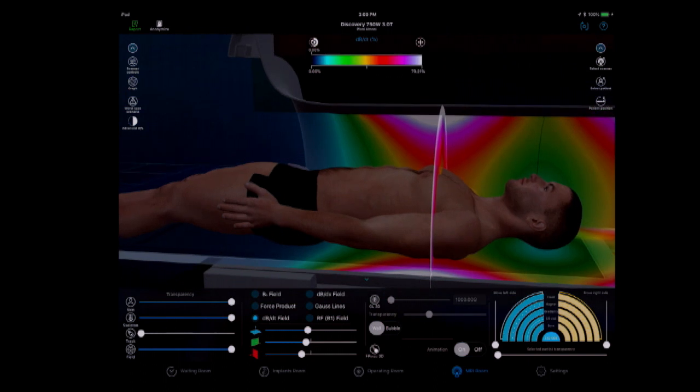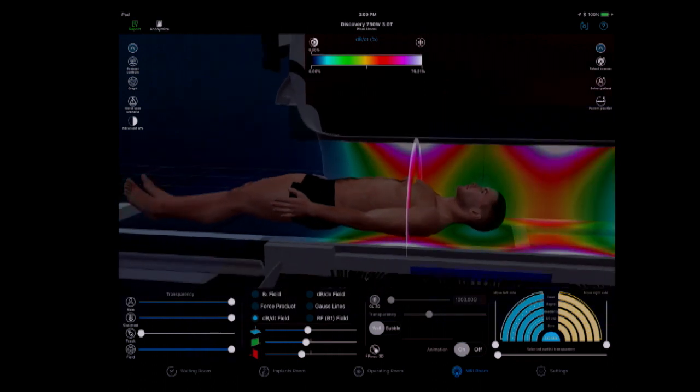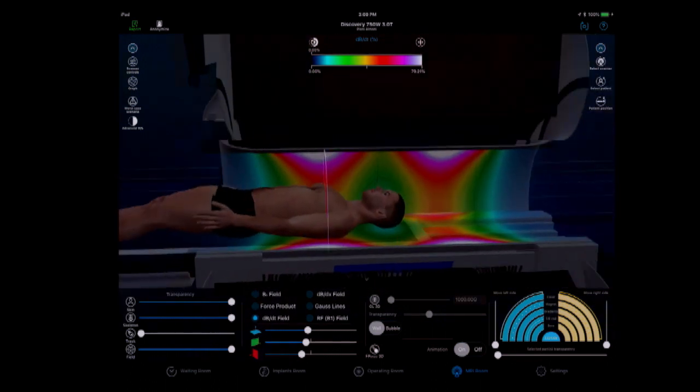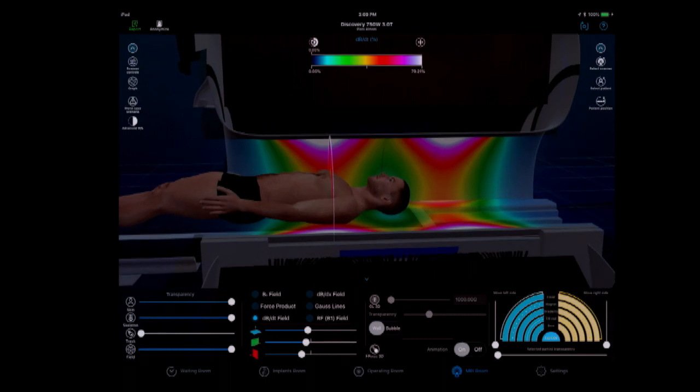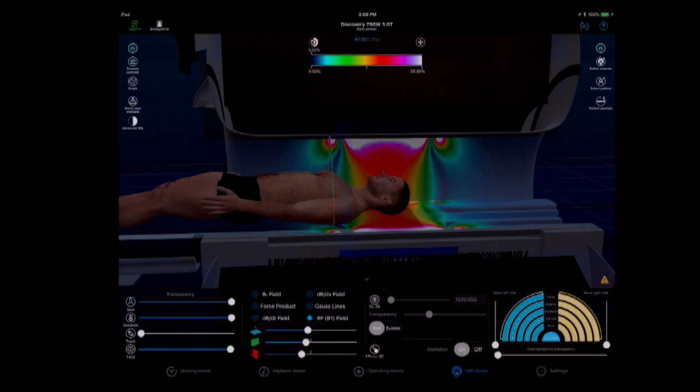So when you center this guy for the pituitary, you max out dBdt right over his pacing system. Do you understand? What will RF look like? What will the RF energies look like? I don't know. What coil are you using? What are the dimensions of that coil? This is the RF for that same magnet.